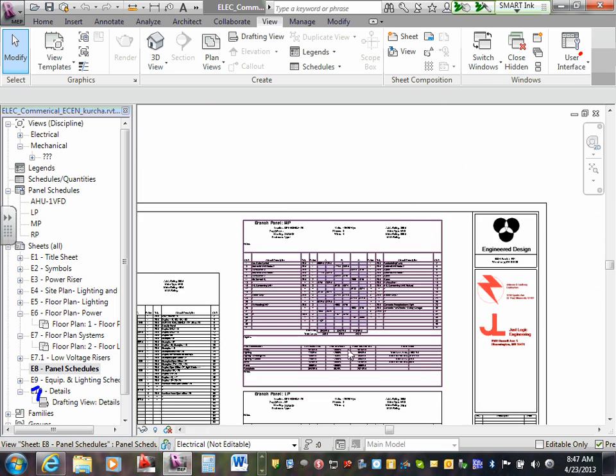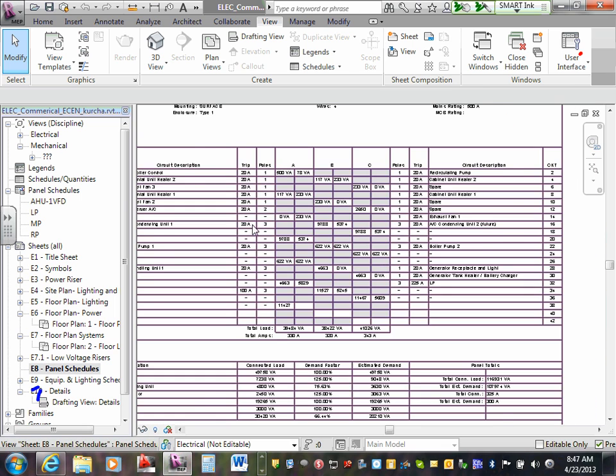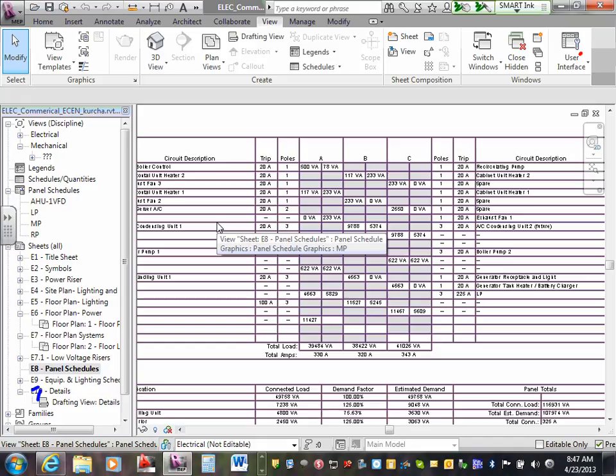Okay, there you go. Okay, first of all, I'm going to see how many receptacle circuits you have, Jeff. Here's my lighting circuit. I'm going to go to how many receptacles. Here's mechanical. By the way, the mechanical equipment, can you guys see the mechanical equipment? This is a home run for each one of them. Except if you have a small load, a tiny little load, then you can group them together. Feel free to group them together. But for the most part, if it's an air handling unit, you'll take a home run from the EMT conduit all the way to the disconnect, and from the disconnect, flex it all the way to the equipment.